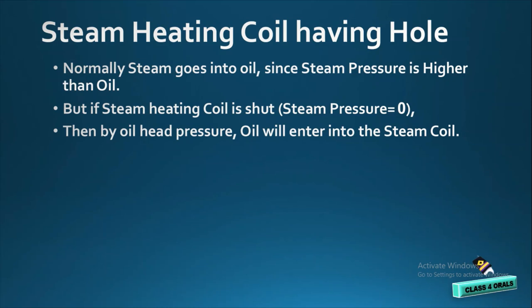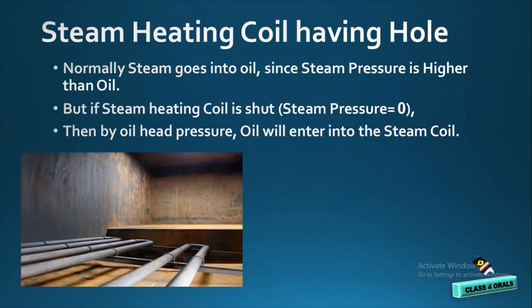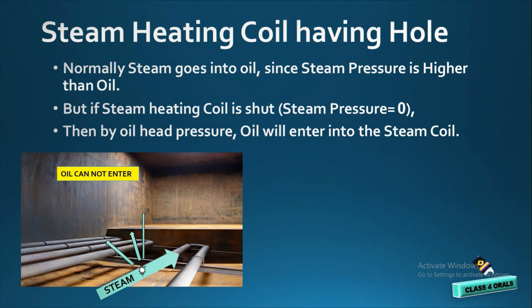One of the reasons of oil getting into the hot well is the steam heating coil having a hole. Let us suppose this is the steam heating coil and it is having a hole in it. Now, the steam pressure is higher than the oil pressure. Because of this hole and steam's higher pressure, the steam can easily enter into the oil side, and oil cannot enter into the steam pipeline.